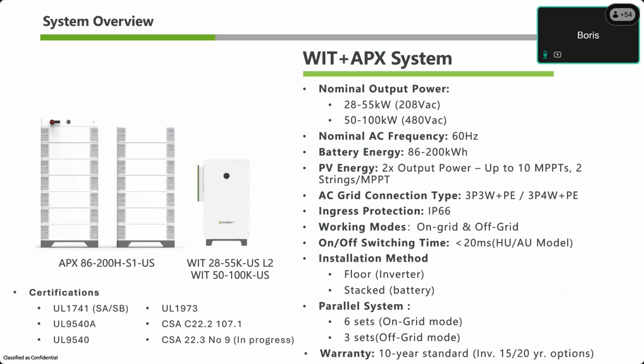Really quick, with regards to certifications, we have all the main US certifications: the UL 1741 with supplement SA and SB, 1973 on the batteries, 9540 for the system, and 9540A for the batteries as well. And then for the CSA cert, we have 22.2 107.1. And we are in progress to get 22.3 No. 9 listed on our certificate as well. Even though it's not an inverter cert, it's really good to have it on the cert. So we're getting that soon.